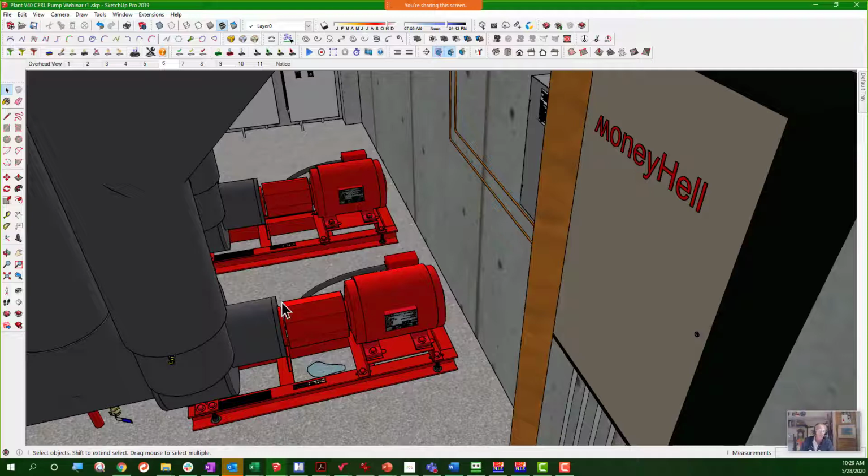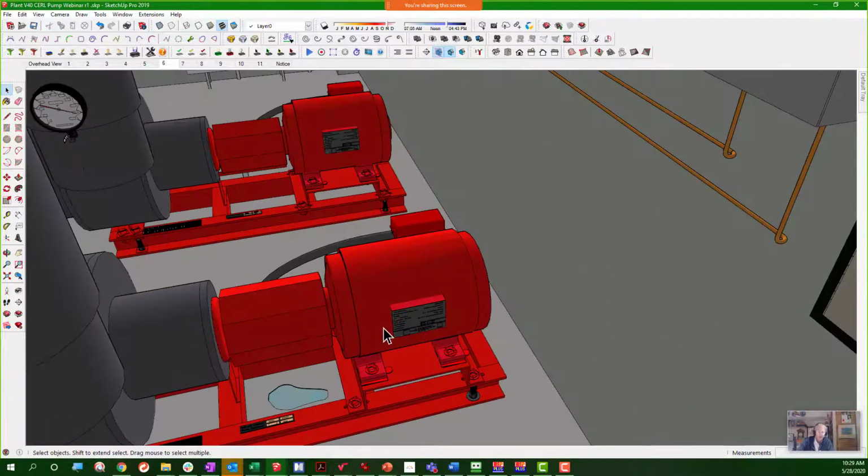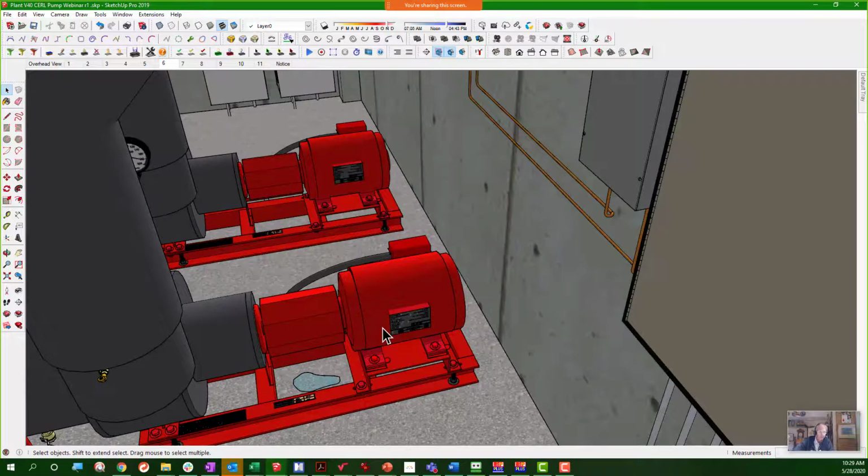But if they're going to spend $60,000 or $70,000, the only thing that the energy has to justify is the 9% price difference between putting in a pump just like this and that best efficiency pump. And so it totally changes the economics. So anyway, that's why I went to that pump.